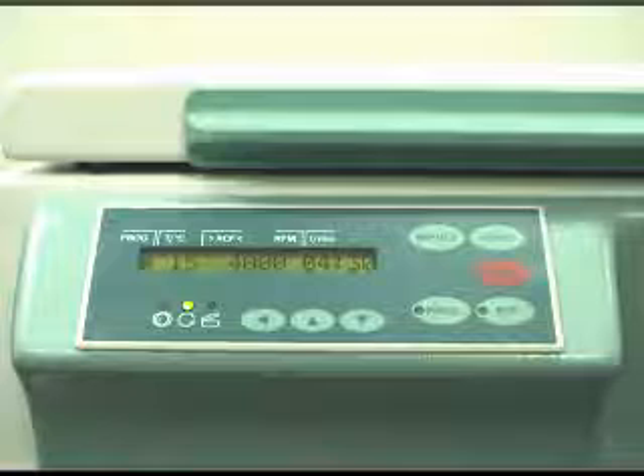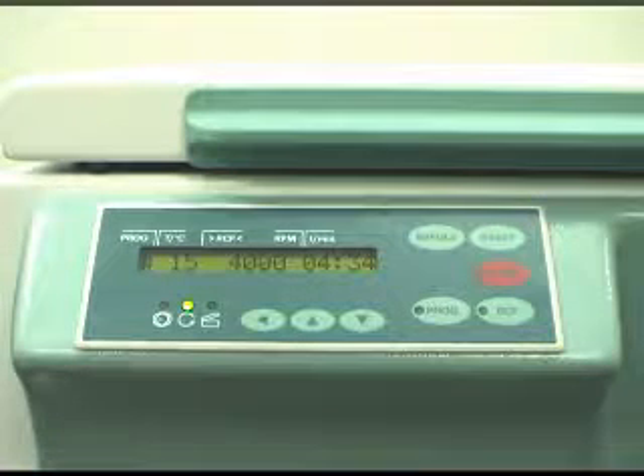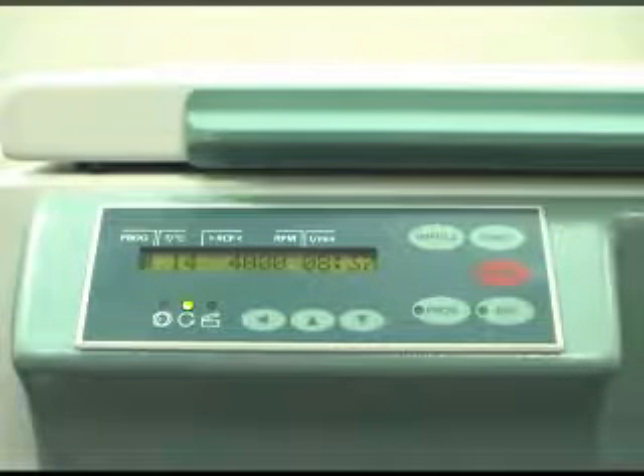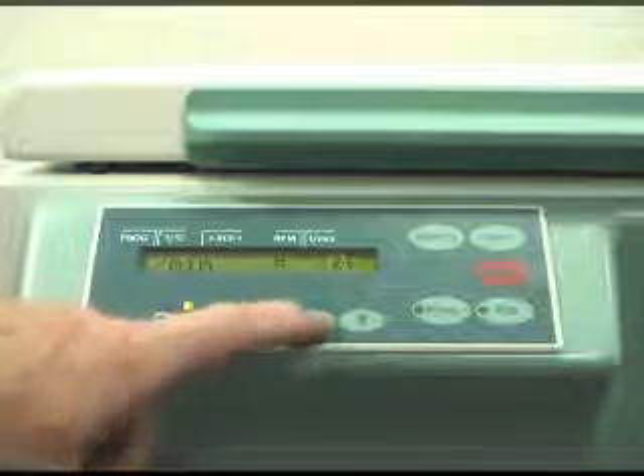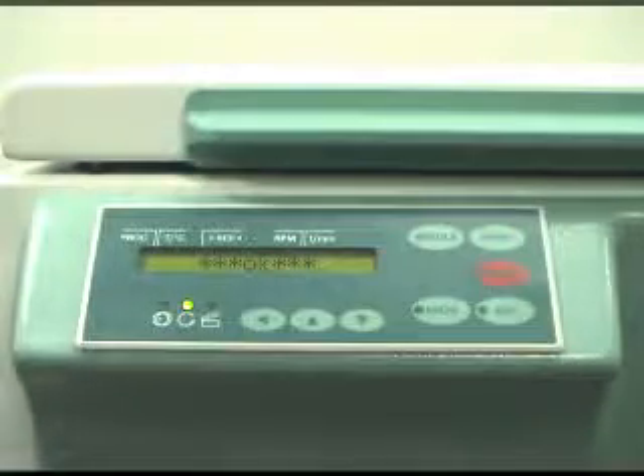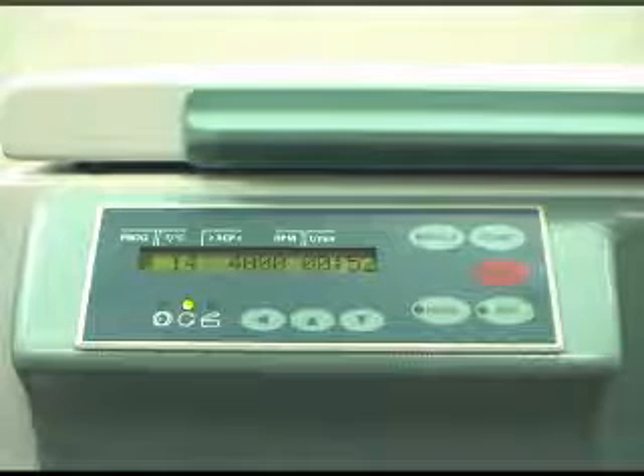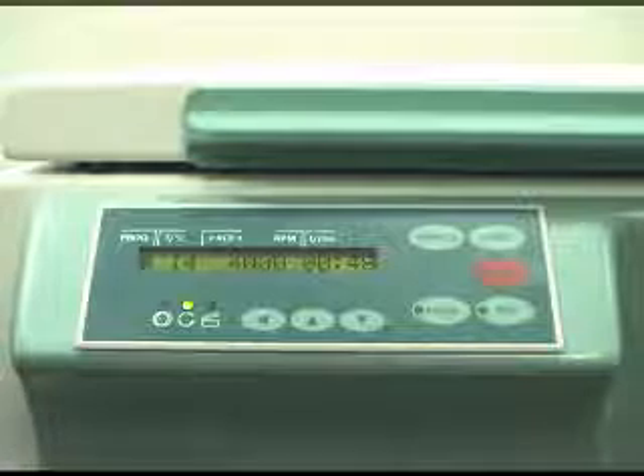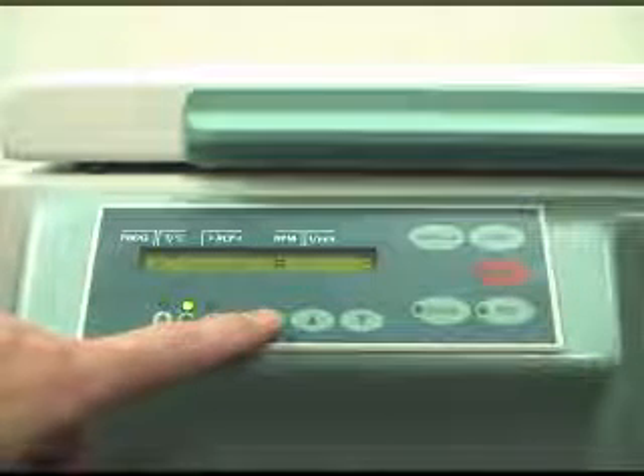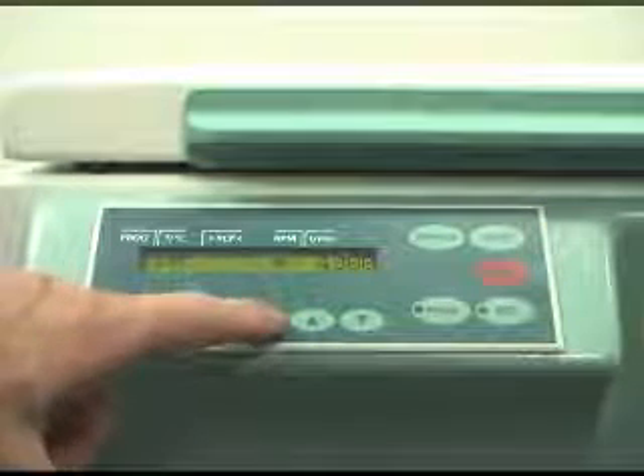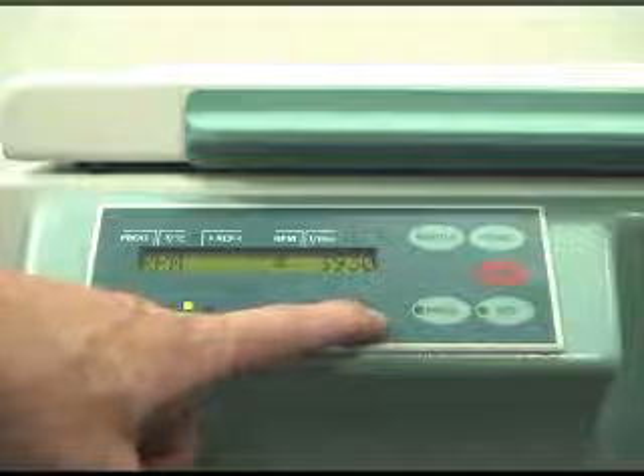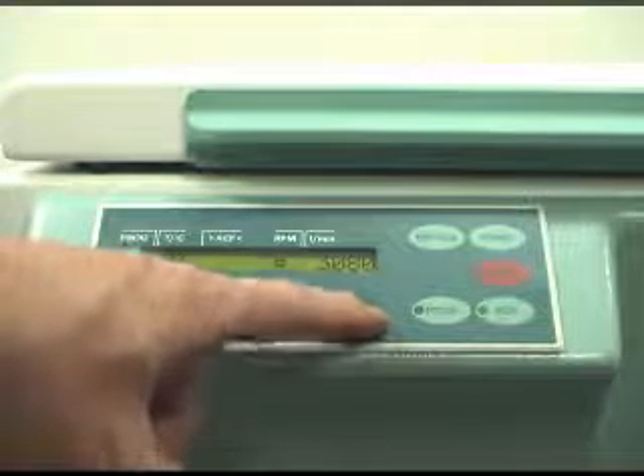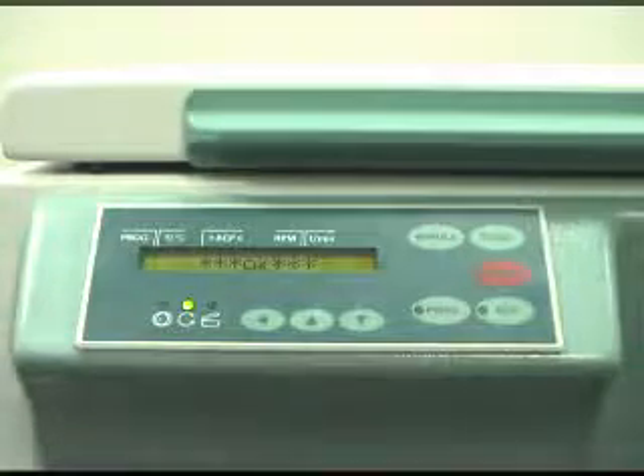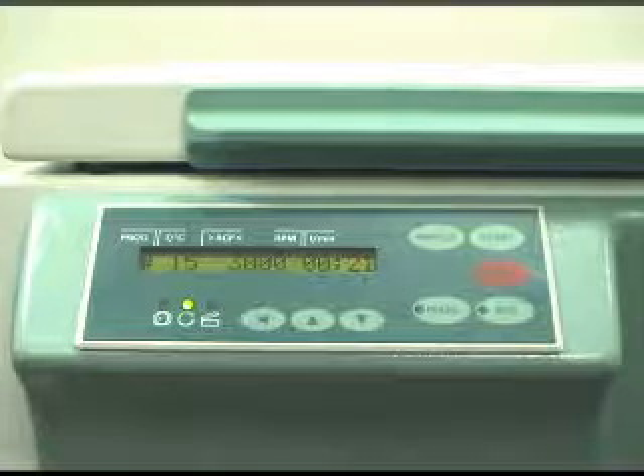For the sake of speed, we edited some of this video so that you would get down to temperature. While on the fly, we can also change the parameters. In this case, it just changed the time to 1 minute, and instead of counting up from 0, it's now counting down from 1 minute. You can also adjust the speed on the fly as well, reducing the speed here to 3,000. Again on the fly. Pressing the start button confirms with an OK in the control panel LCD.